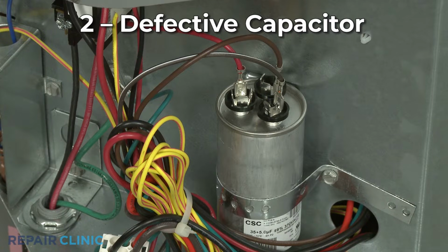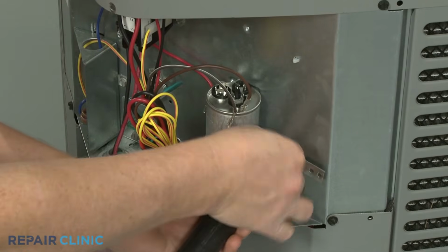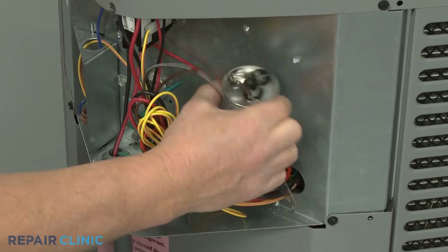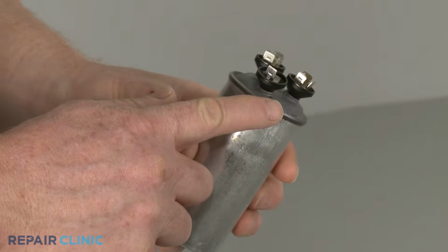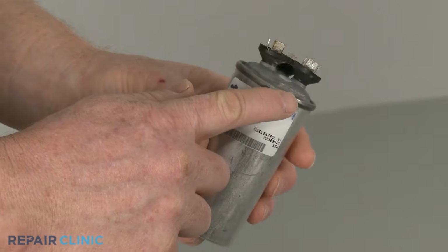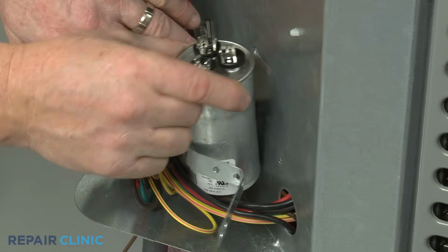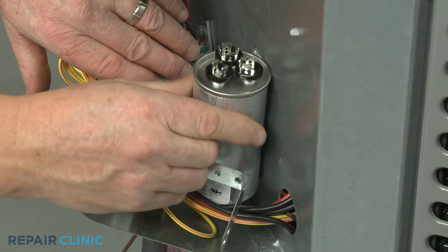A single-run or dual-run capacitor stores an electrical charge, then releases it to power the fan motor in the condensing unit. If the capacitor is defective, the fan motor may not run at all. When a capacitor fails, it will often bulge or leak. If you observe any bulging or leaking, the capacitor must be replaced.